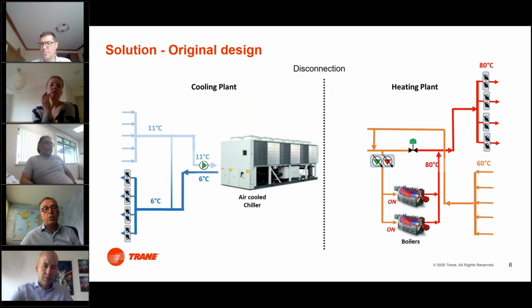So that's what we did, and we approached this from an initial standpoint of a disconnected cooling and a disconnected heating system. That was the original plant. There was this air-cooled chiller, an older-style air-cooled chiller that needed to be replaced. Again, the efficiency of that unit would potentially double with the new innovations. And then we had the heating plant that was disconnected and using fossil fuel to heat.